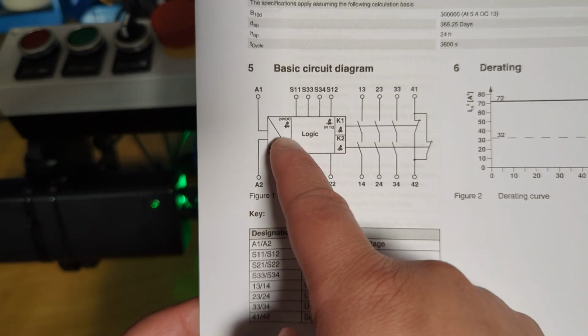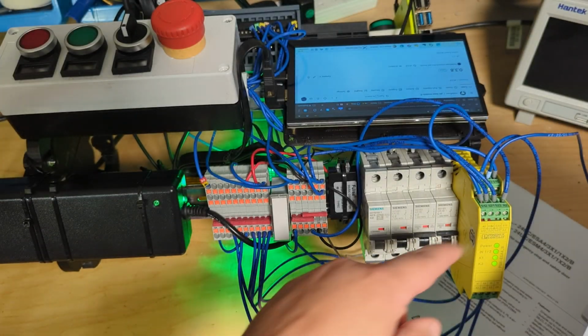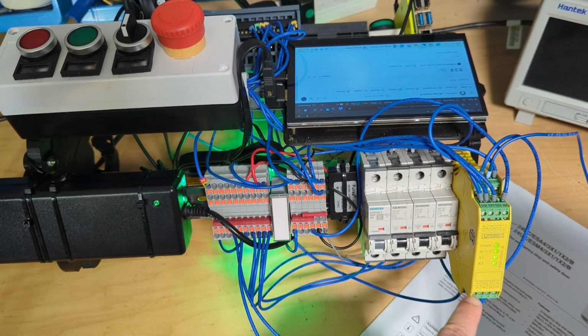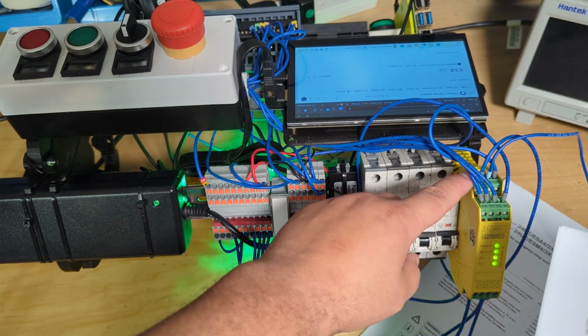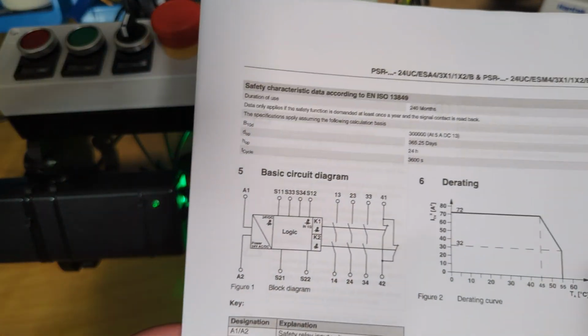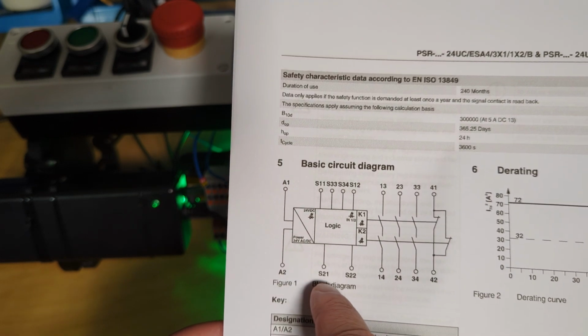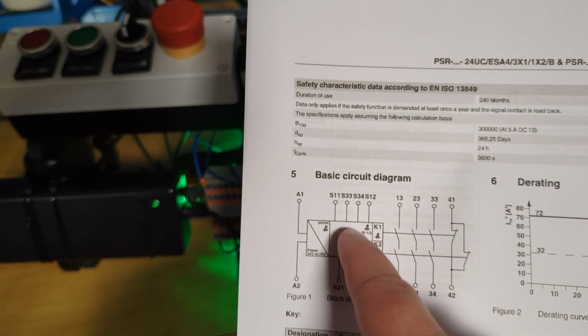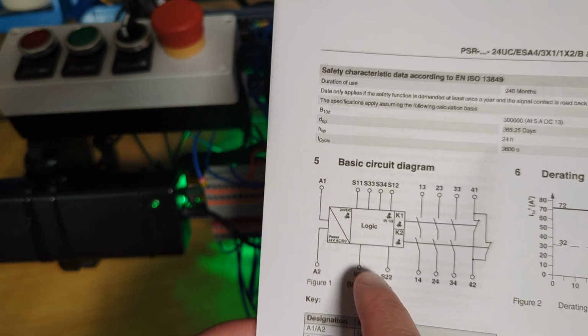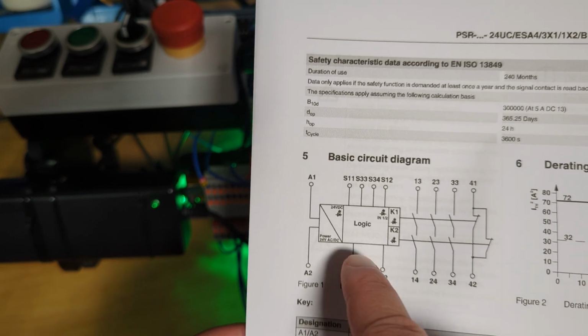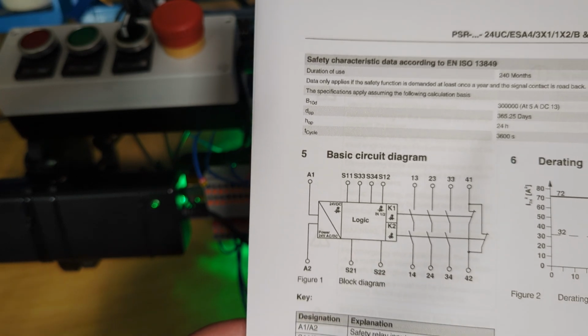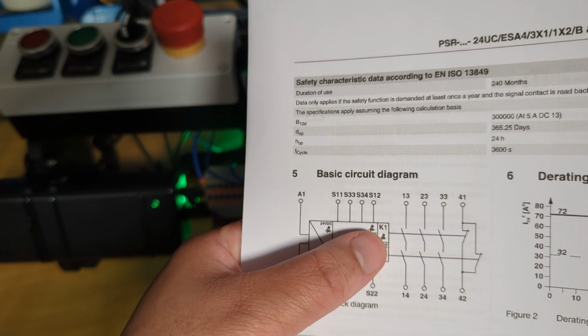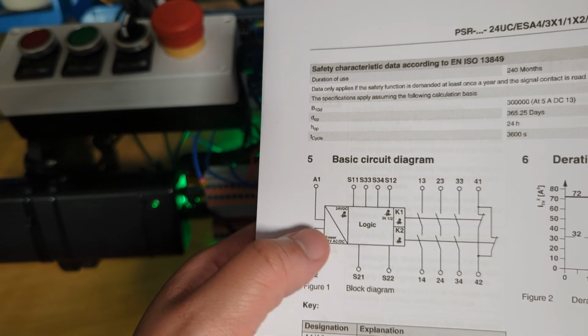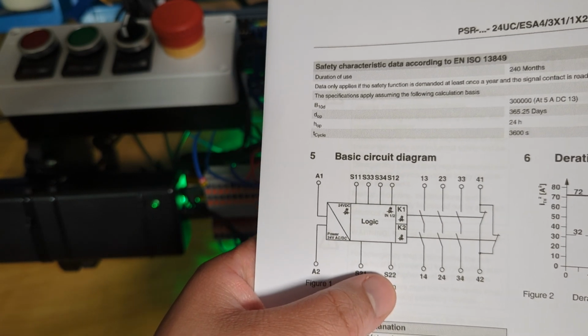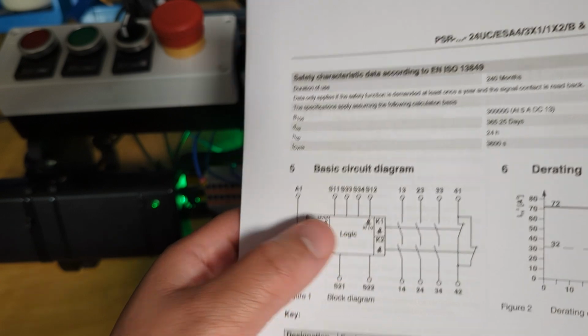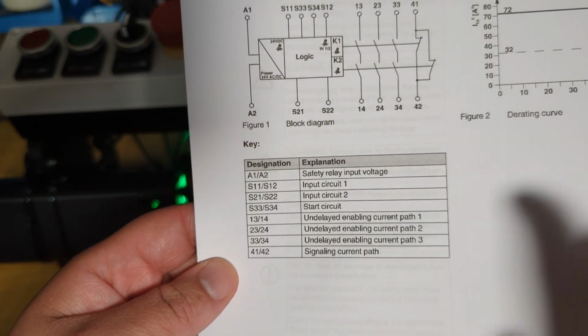So we've got power being supplied into the safety relay via A1, A2. Power comes in at 24 volts, and then you've got your logic, which is where you pass in your input. This safety relay can take in three inputs. I'm only using two. It can take in S11, S12, which is one channel on my e-stop, and then S21, S22, which is the other channel, and then S33, S34. So you can see the explanation of that.